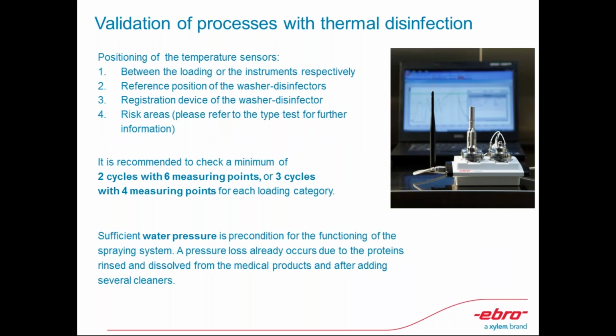Now we go to validation of processes with thermal disinfection. There are some procedures that we have to note before implementation. The positioning of the temperature sensors. When you look at the positioning of the temperature sensors, and look at 1, 2, 3, and 4, and you look at the catalog with our logger with 4 sensors with flexible cables, this is going to solve this procedure with a lot of convenience and accuracy.